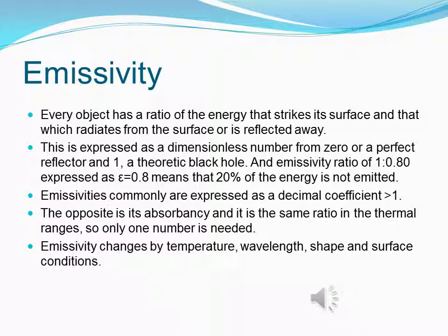More of that heat's going to be given through that insulation, even though it's a poor conductor. Sometimes more can be given through that insulation than the conductor itself, until it gets hotter and starts to oxidize. So you need to understand emissivity and how it applies to each small piece of the picture that you're looking at, because it can change from piece to piece, condition to condition.